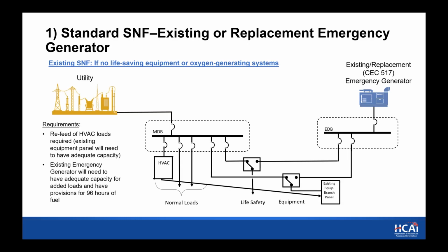So we put together a couple of single lines, and each of these will be a standard SNF, and then there'll be a drawing that is basically the same that looks at acute care and subacute. So the existing SNF, we're assuming, has no life-saving equipment or oxygen generating systems. If you look over to the right, we have on the top the existing replacement emergency generator, and that currently feeds the emergency distribution board, which feeds 2 transfer switches.